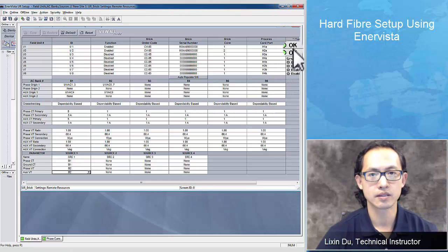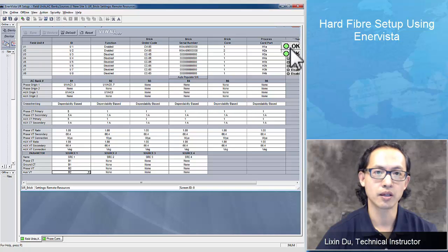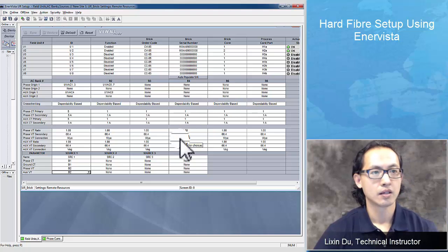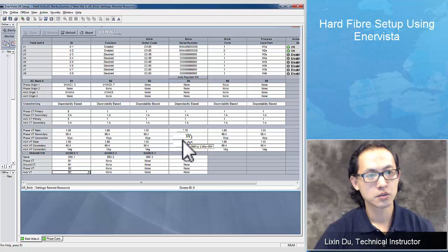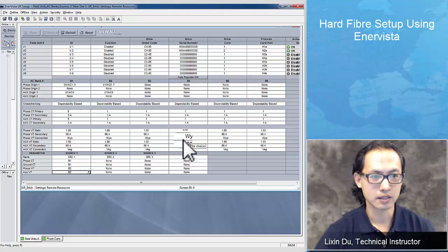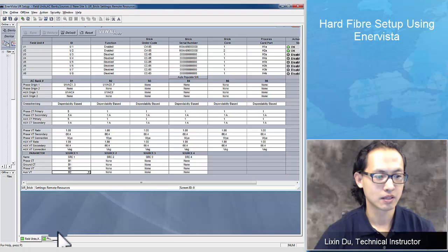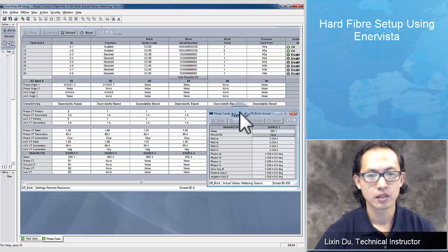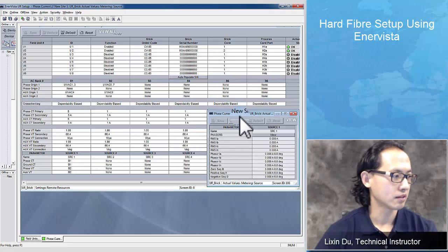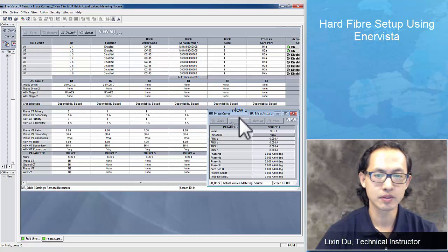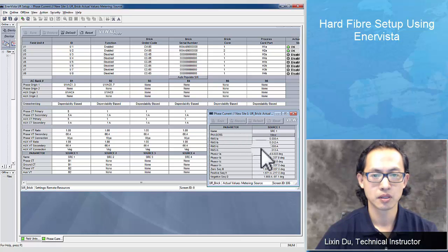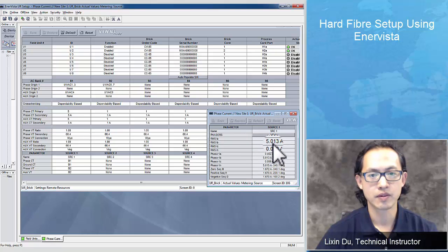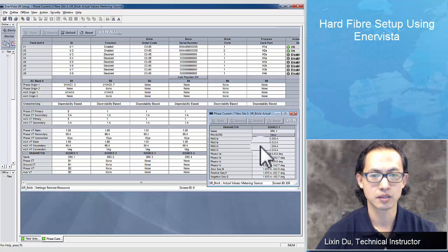Now we can see that the status has changed to OK. Once you've done all these settings, you have to reset the relay to make these settings effective. For now, I just apply the current again, 5 amps to the phase B current, and I'm going to verify these values displayed in the meter screen.